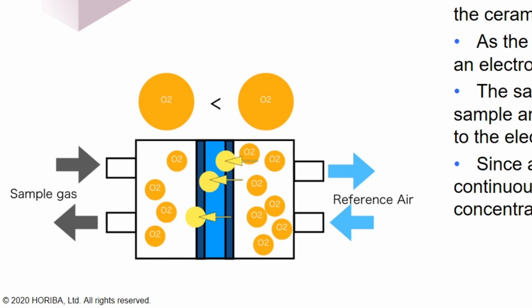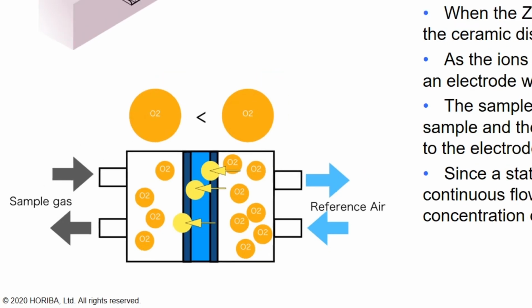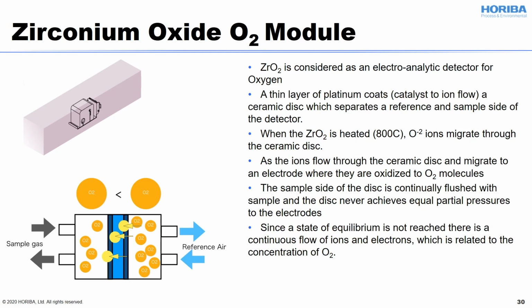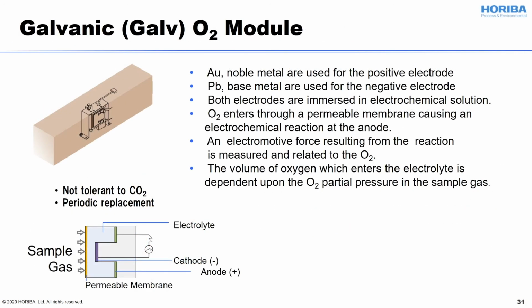You have 2 chambers divided by the ceramic disc. One chamber is continuously fed by sample gas, and the other one is fed by reference air. Oxygen migrates from higher concentration to lower concentration to reach a balance. The zirconium method detects this migration, which is related to the concentration of O2. Lastly, galvanic O2 modules: there is an anode and a cathode, and both electrodes are immersed in an electrochemical solution. O2 enters through a permeable membrane, causing an electrochemical reaction at the anode. An electromotive force resulting from the reaction is measured, and it is related to the oxygen concentration.